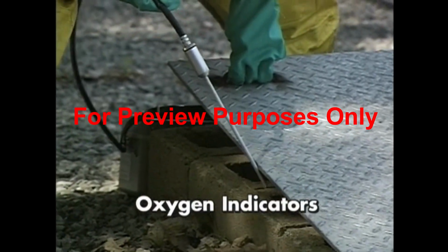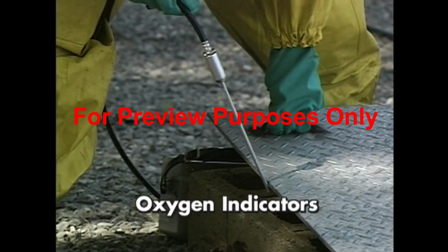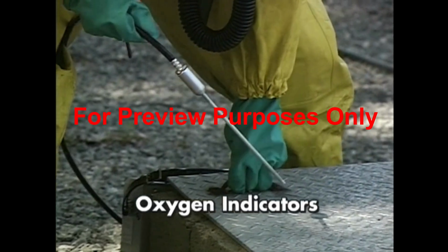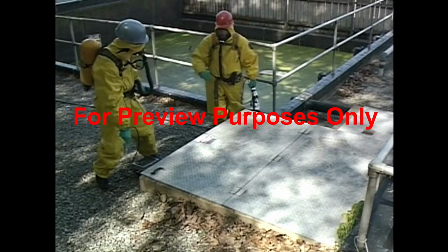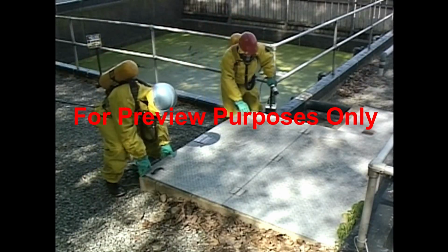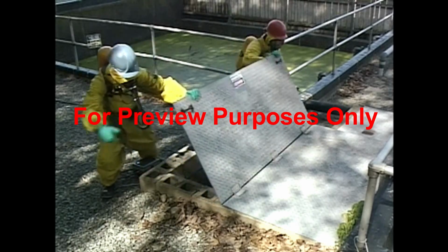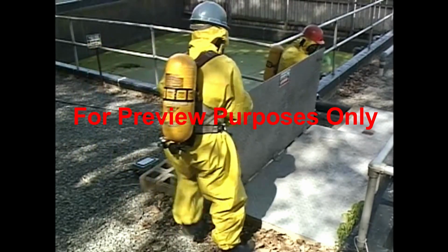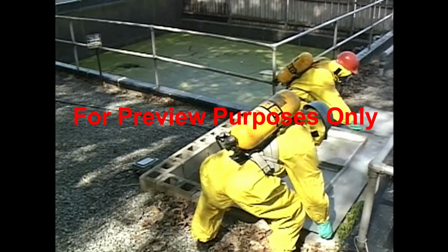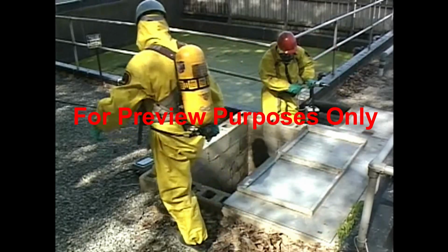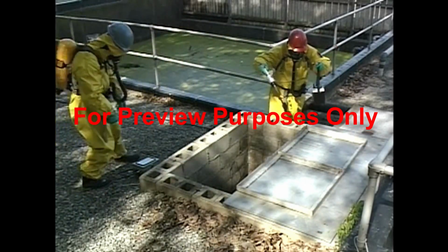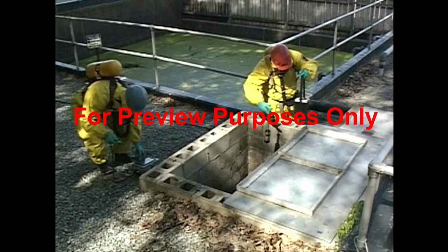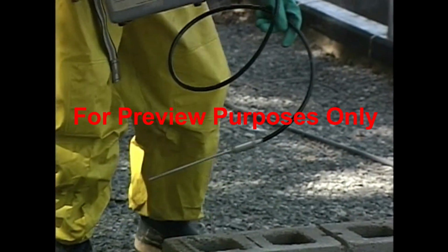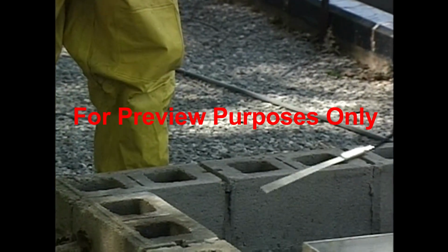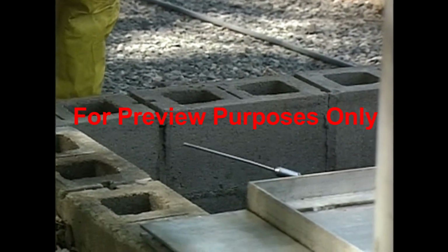Oxygen indicators use electrochemical sensors to determine the oxygen level of the air around you. This is important because if the oxygen level falls below 19.5%, there will not be enough oxygen for you to breathe. If the level rises above 23.5%, the atmosphere will become combustible. This means that there will be a significantly greater chance for a spark or other ignition source to cause a fire or explosion.